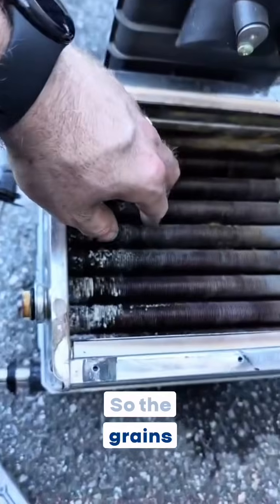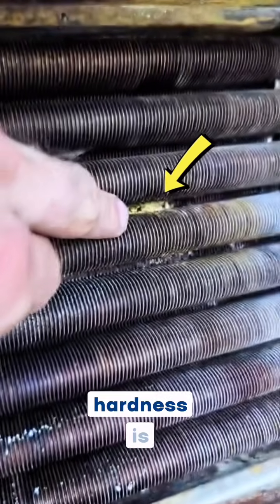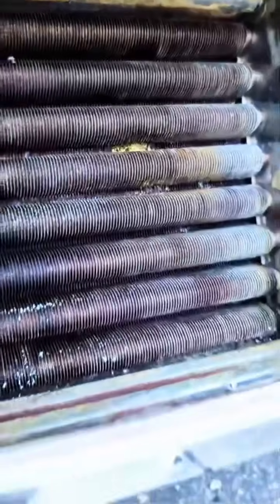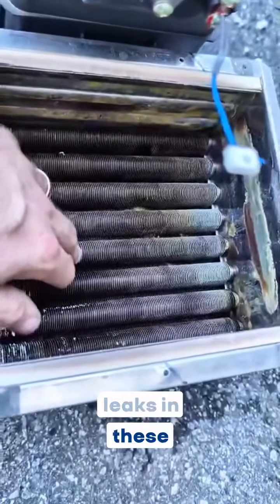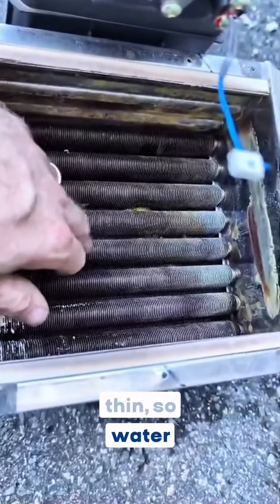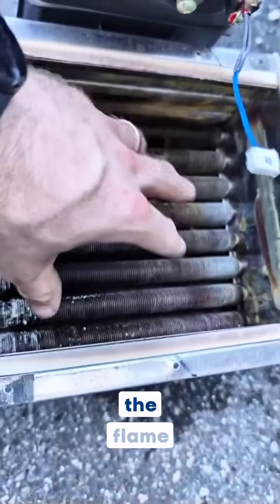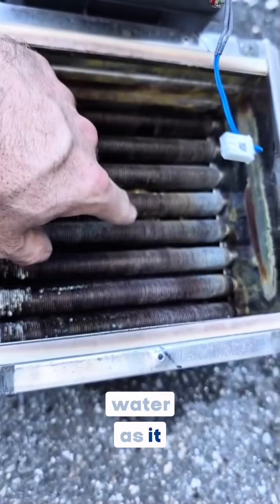So the grains per gallon hardness is what's going to cause this type of buildup in here. It's going to cause pinhole leaks in these fin tubes, and these are very thin, so water has to go through that. This would be where the flame would be, heating up the water as it passes through these tubes, but those tubes are also very thin.